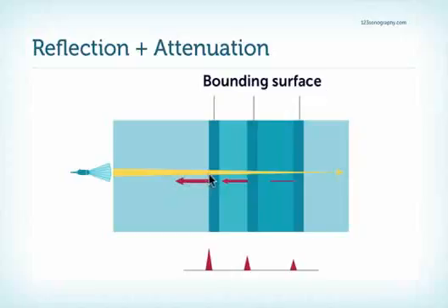Well, we said that we have a reflection if we have a boundary. But in tissue, in reality, we have not only one boundary, but multiple boundaries. And part of the ultrasound beam penetrates, so we have multiple reflections. Obviously, these ultrasound reflections will not all return to the transducer at the same time. The further away the reflection occurs, the longer the time until it is again received by the transducer.